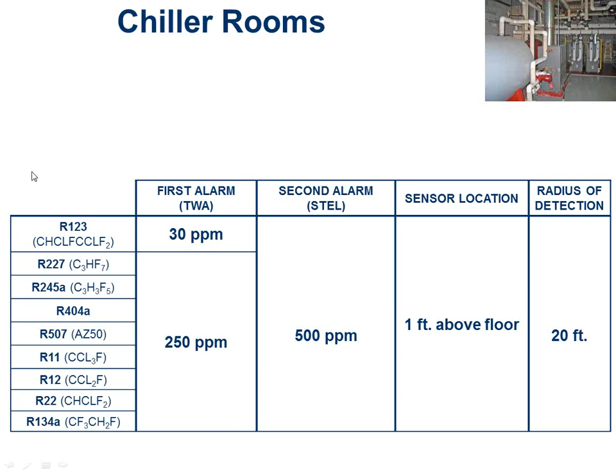ASHRAE Standard 15 is what governs most building codes for chiller room concerns. I got the 2007 version up on here. I believe the newer one has the exact same language, so I didn't bother changing it. Plus, most of your codes are still following old standards anyway. But basically, the ASHRAE standard is going to tell you that you need to have a sensor for each refrigerant that you're expecting to have in that room, right? So you need a 134A, you need an R11 if you have that, those kinds of things. You have to locate it near the equipment so you can sense it properly. You have to control it to the recommended TWA for that particular refrigerant. You have to have visual and audible alarms inside the chiller room and outside every single entrance to the chiller room so nobody goes in there when there's a problem, right? So that's the main catch on that.